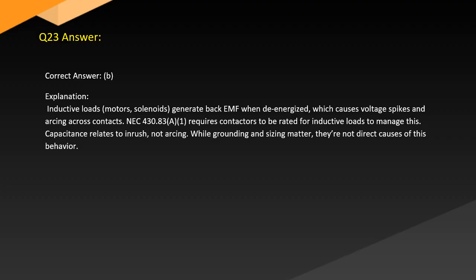Answer. Correct answer: B. Explanation. Inductive loads, motors and solenoids, generate back-EMF when de-energized, which causes voltage spikes and arcing across contacts. NEC 430.83(A)(1) requires contactors to be rated for inductive loads to manage this. Capacitance relates to inrush, not arcing, while grounding and sizing matter, they're not direct causes of this behavior.